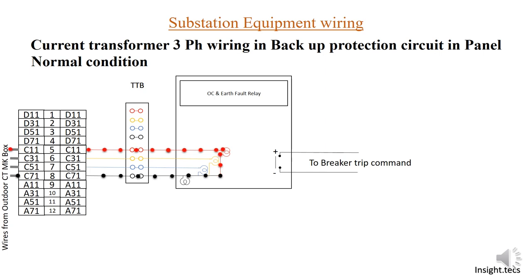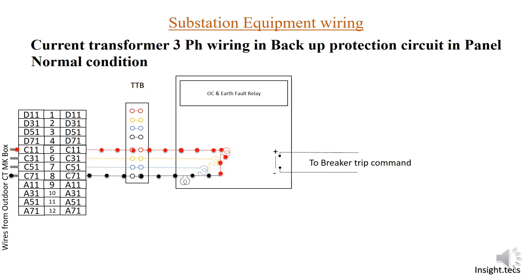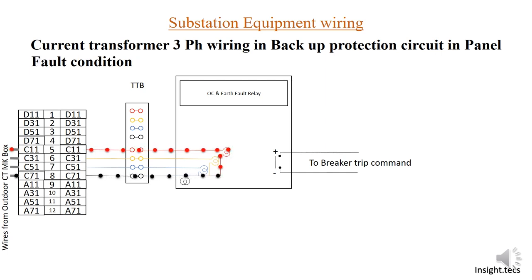In normal condition, this is how the current flows into the overcurrent earth fault relay through the TTB from the wires coming from the current transformer. Now, when there is overcurrent or a fault in the CT, a greater amount of current flows in that phase. You can see the overcurrent flowing through the TTB into the relay. Due to this overcurrent, a trip command is sent to the breaker. Once the trip command is sent, the positive meets the negative, the circuit is completed, and the breaker trips.